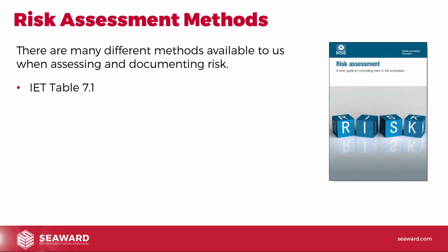It's not really a risk assessment process, and remember, we are legally charged with carrying out risk assessment. It doesn't say just picking values out of a table. So you probably would still need to do risk assessments, even if the result was that you said, well, the control measure I'm putting in place is that I'm going to assess based on this table. You probably still need to document the risk in the first place. What I haven't included in this list, because it's not really a method at all, is the every 12 months process. Similarly, any fixed arbitrary time that somebody says, 12 months, 18 months, 2 years, whatever it is, is not a risk-based method. It's just an arbitrary figure that somebody's arrived at.